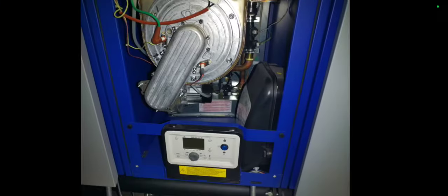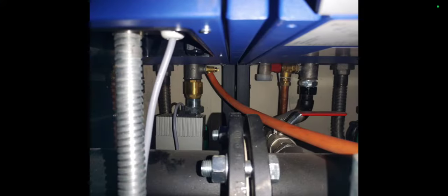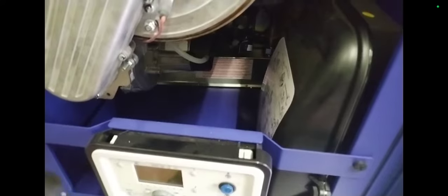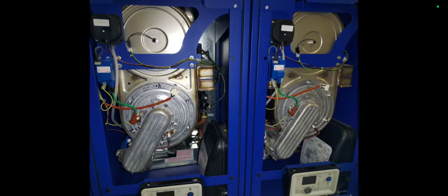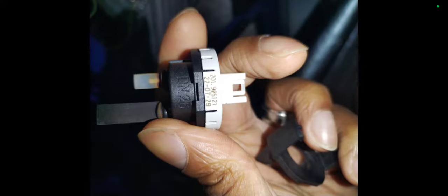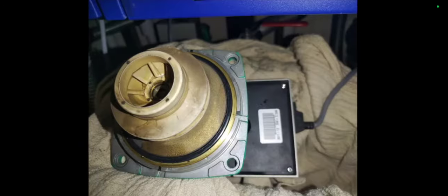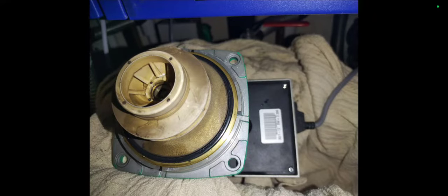So out of that plant room and finishing servicing onto another plant room where we had some boilers overheating. And I was just checking the different things like the pressure sensor and the flow sensor. There's the flow sensor there. This is a Hamworthy. Got a few units in here. And this is the flow sensor I checked. And there's a pump on the unit that had seized. So here's the pump seized on one side.